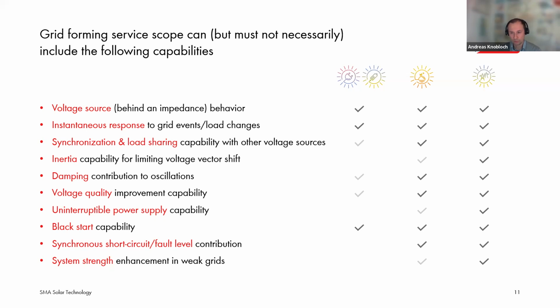Voltage quality improvement capability, so not necessarily to ensure an own voltage provision, but to improve a voltage quality whenever the voltage quality is poor. Uninterruptible power supply capability, black start capability, synchronous short circuit fault level contribution, system strength enhancement in weak grids.